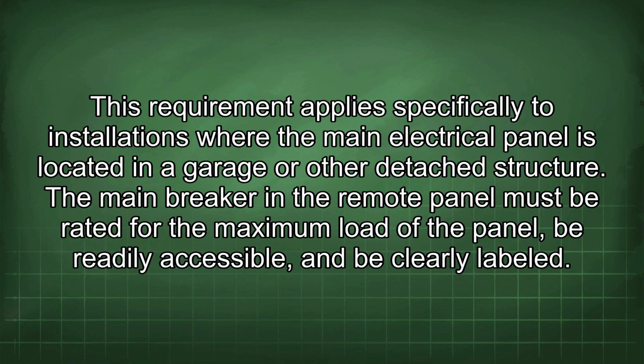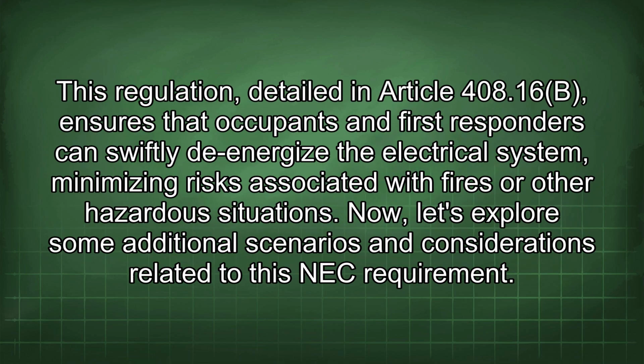The main breaker in the remote panel must be rated for the maximum load of the panel, be readily accessible, and be clearly labeled. This regulation, detailed in Article 408.16b, ensures that occupants and first responders can swiftly de-energize the electrical system, minimizing risks associated with fires or other hazardous situations. Now, let's explore some additional scenarios and considerations related to this NEC requirement.